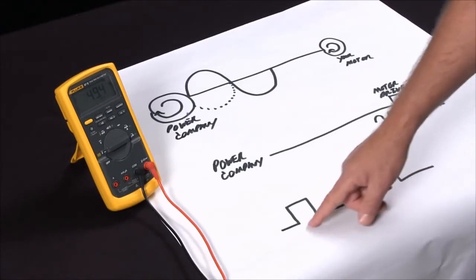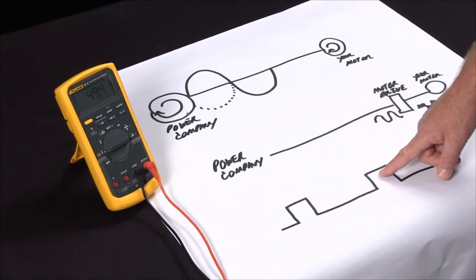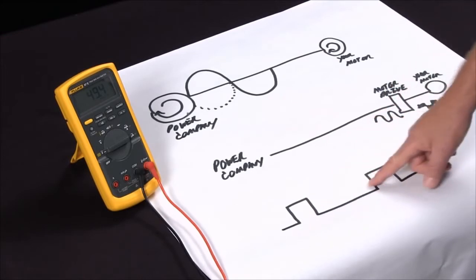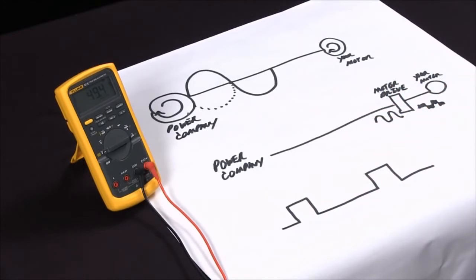This is very handy if you're looking at an encoder where you have a square wave. You would like to see the pulse maybe 25% on, 75% off is a properly set encoder motor. And so this is how you can use the Fluke 87 to measure frequency and duty cycle and actually measure frequency much more accurately on motor drive systems.